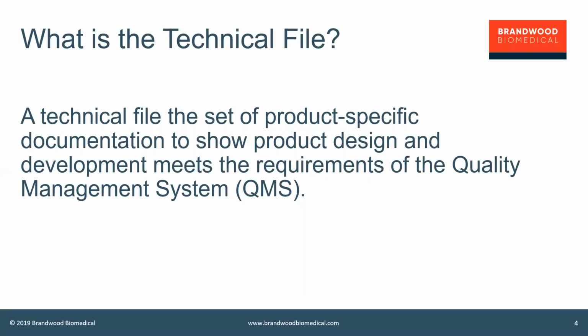So basically, a technical file is really the product-specific documentation to show the design and development of your device meets the quality management system requirements. That's the bottom line. It's as simple as a set of documents that basically show that you're doing design and development aligned with your quality management system. Now, as medical device and IVD manufacturers, we have standards that we must comply to with our quality management system. So by ensuring that your technical file is aligned with your QMS, it will also be aligned with those standards.